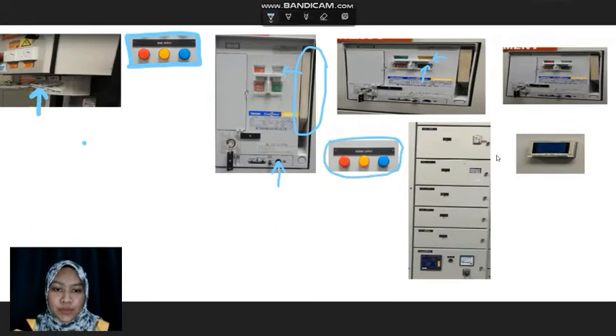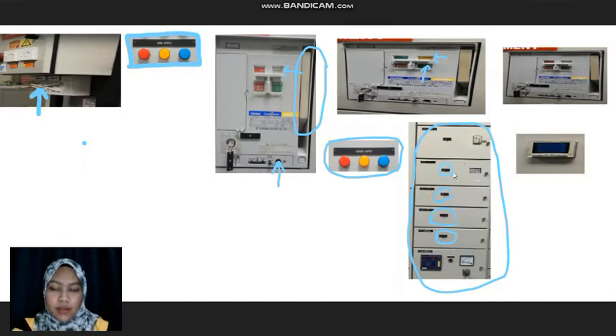Now we are going to turn on the loads, or MCCB. Before we turn on the MCCB, we must inform the consumer side first. After informing them, we turn on the power factor capacitor and then we turn on the MCCBs one by one, by pushing them to the left. After we turn on all the loads, we check the current status of the system. Now the process is complete, MSB1 is energized, and the supply is already given to the consumer.